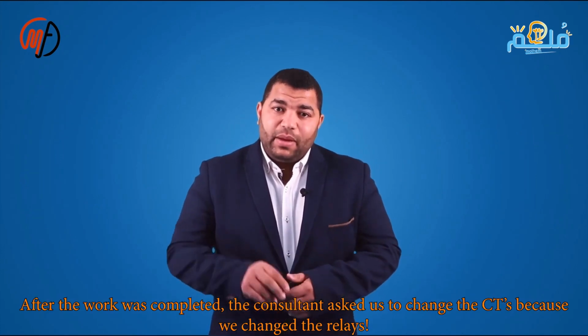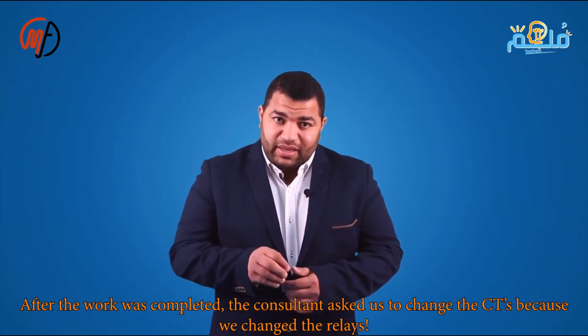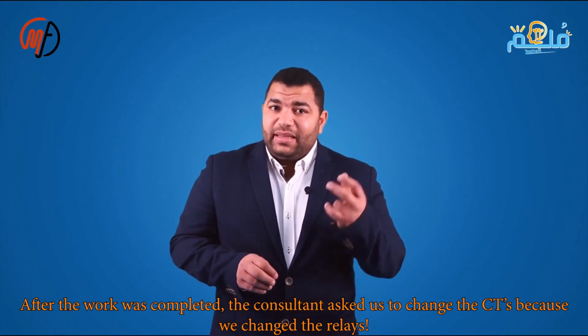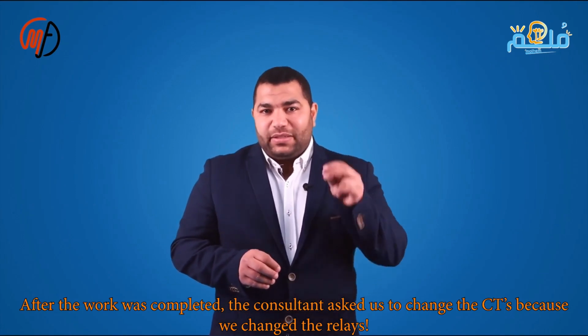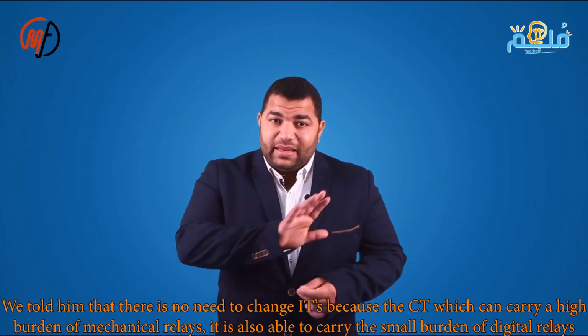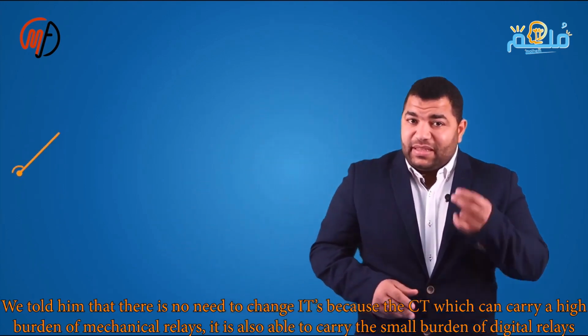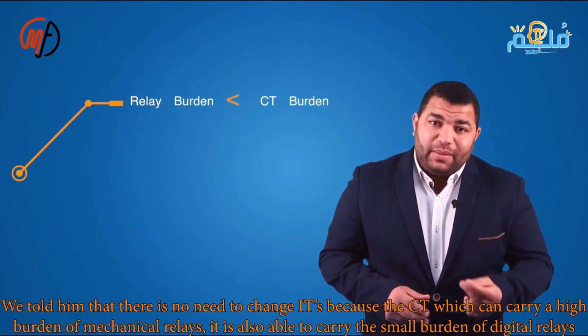We were consulted about CT changes for the new digital relay. We advised no CT change was needed as it handles both high and low burdens. The CT's knee point must exceed the secondary terminal voltage when connected. This influenced CT change decisions, sometimes adding costs.